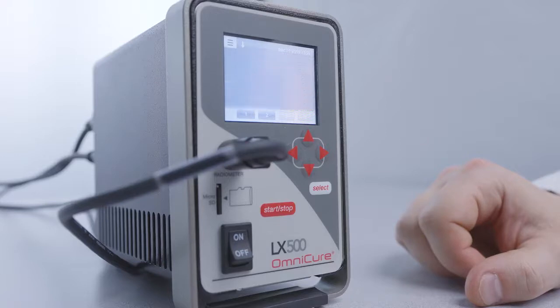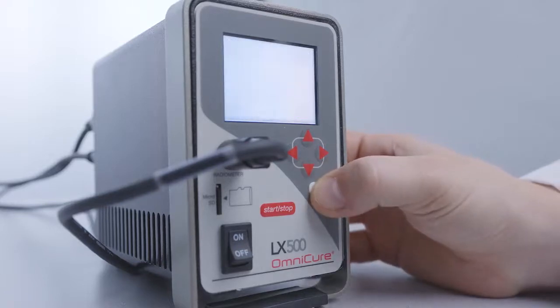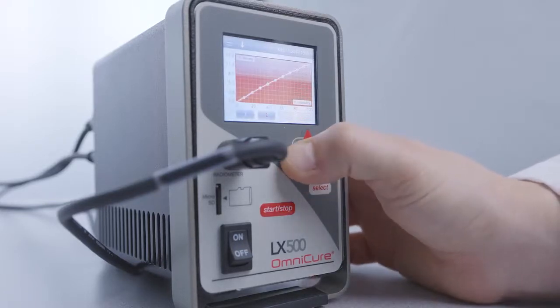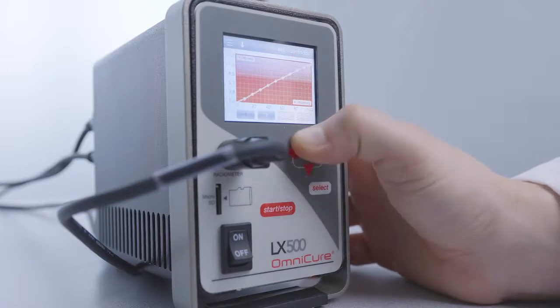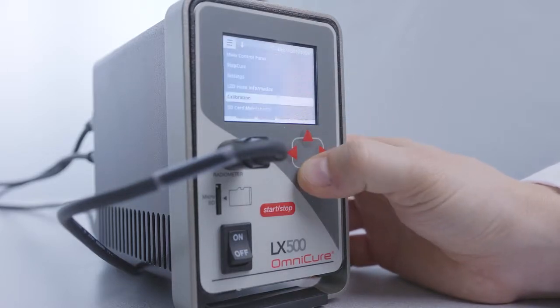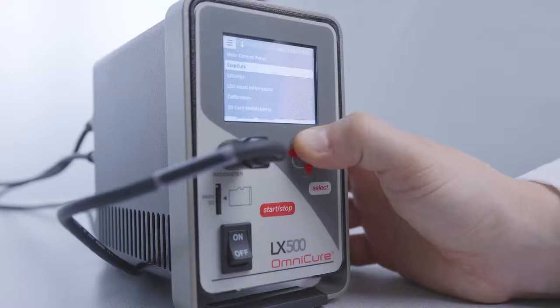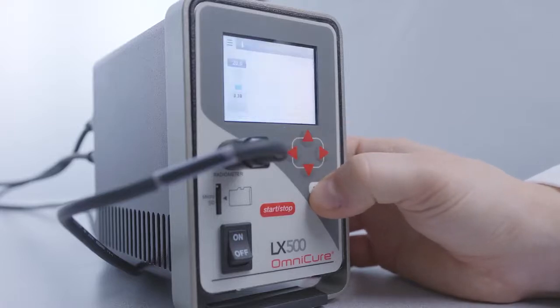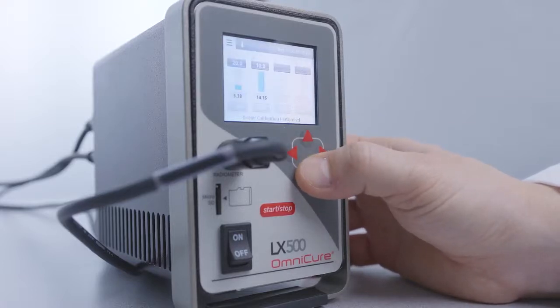pressing Select. Once the calibration is complete, it will remain in the system for up to 100 hours, and intensity will be displayed in watts per centimeter squared on the main screen. If the LED head is disconnected, the calibration will clear automatically. The calibration can also be manually cleared. Repeat all previous steps for any additional LED heads connected to the LX500 controller.